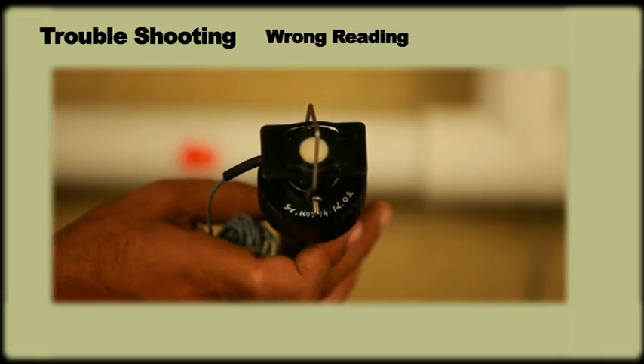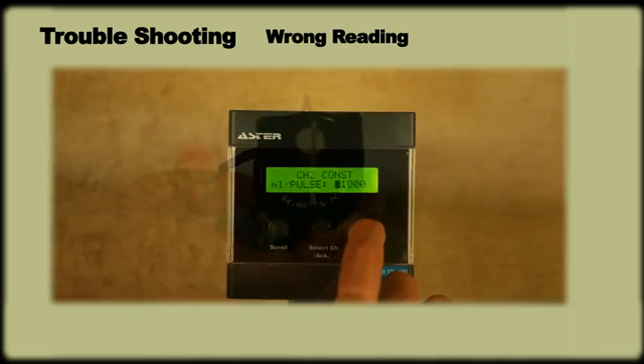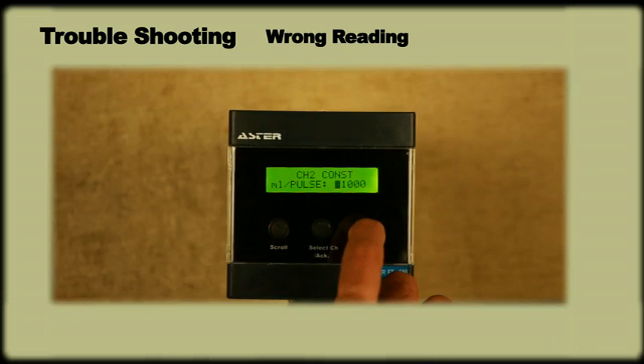In case of multiple instruments, check that the serial number of sensor and meter is same. The scale factor programmed in the instrument must be same as that engraved on the sensor.